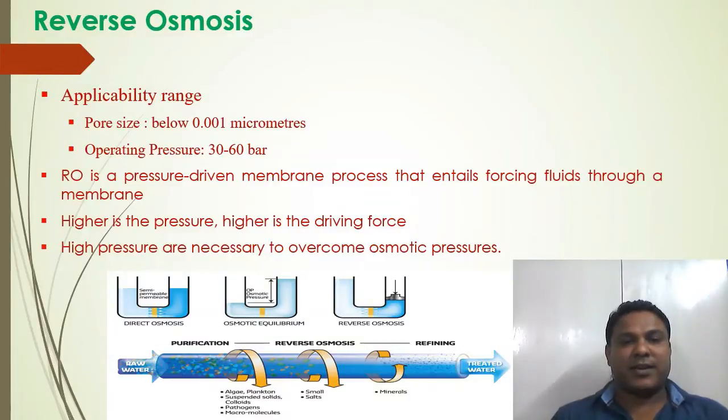So as discussed earlier, reverse osmosis is a special type of filtration that uses a semi-permeable membrane, a thin membrane with pores small enough to pass pure water through while rejecting larger molecules such as dissolved salts or ions and other impurities such as bacteria, viruses and suspended solids.